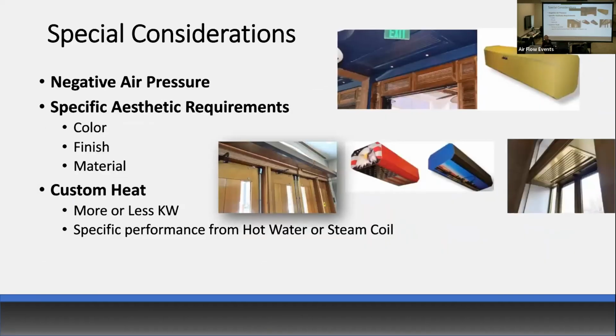Some special considerations: negative air pressure. If you have a severe negative air pressure, I don't care how oversized you make the air curtain, it is not going to stop that air from coming in. It's just basic laws of physics. What we would recommend in that instance is maybe put a heated air curtain there, so at least you're heating the air at the point of entry, making it comfortable. It's not freezing cold air, but an air curtain is not going to stop a severe negative air pressure.